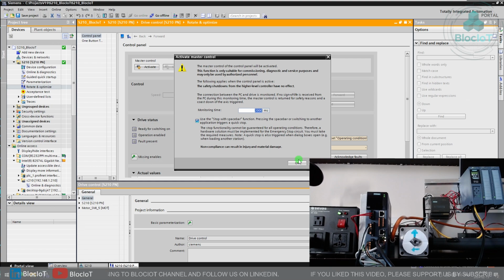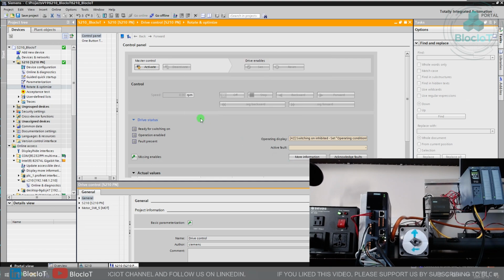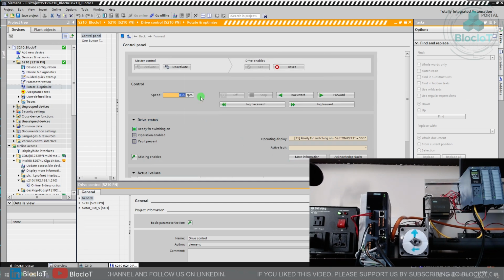Just give it a monitoring time. The default 2 seconds is good enough, and give it a predefined speed. We just give it 60 RPM, that's good enough. And then you click on one of the forward or backward. And as you can see, my motor is moving or rotating, and that's a good sign. It means my drive is healthy, all my wiring has been correct, and we are ready to go to the PLC side.